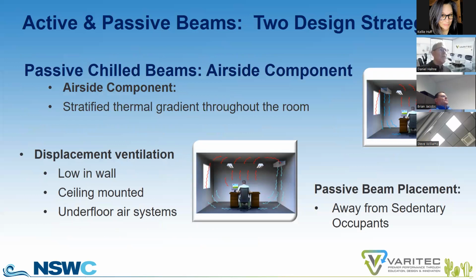So the air side component on a passive chill beam system uses displacement ventilation. I've been involved in a number of displacement projects, very effective. Diffusers are placed low in the wall, and an excellent solution is an underfloor air system. Underfloor air systems are really developing in their capabilities of meeting building loads and needs.